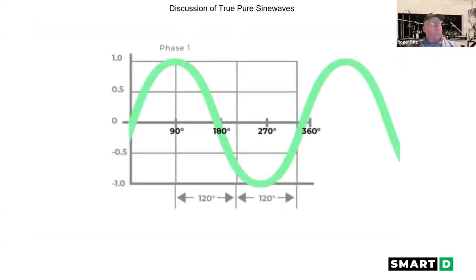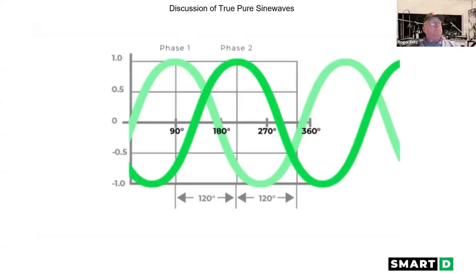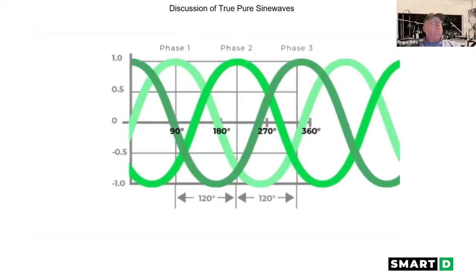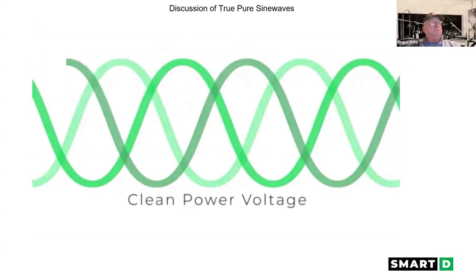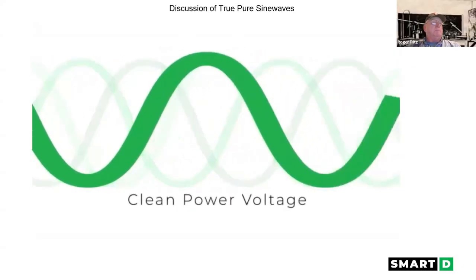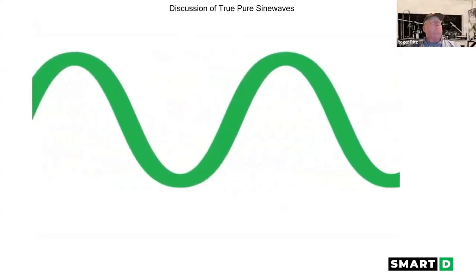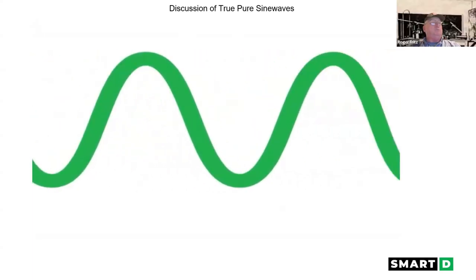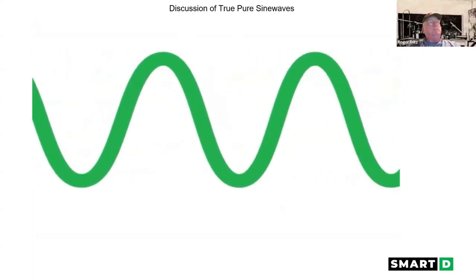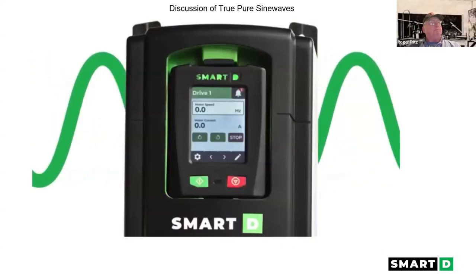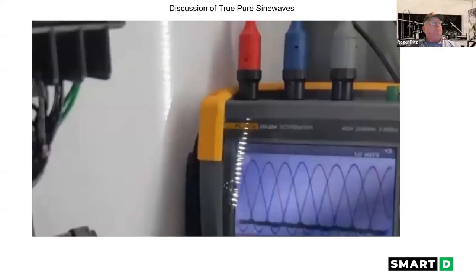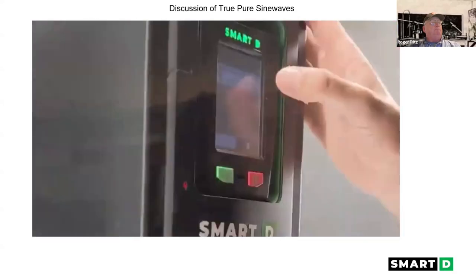A three-phase clean power VFD produces three smooth sinusoidal waves, which at any point average a sum of 0. This creates an optimal scenario with zero common mode over voltage. The best solution to mitigate common mode voltage is to not generate it. A clean power VFD produces a clean signal with no need to mitigate common mode voltage.